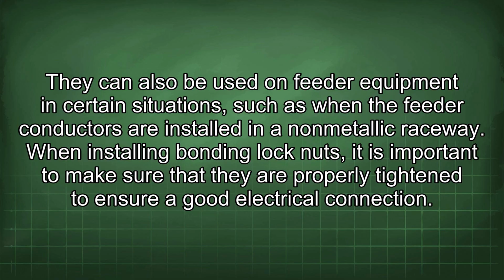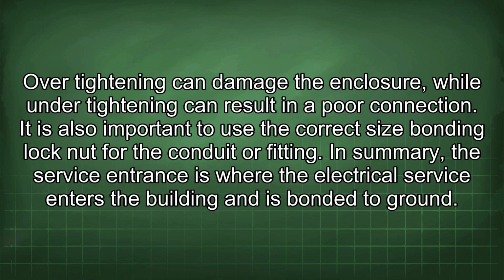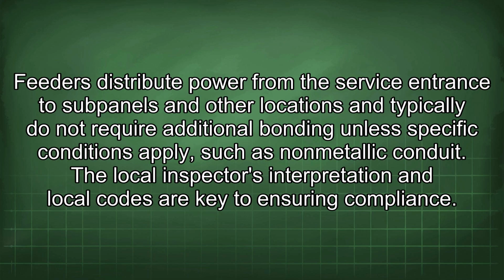When installing bonding lock nuts, it is important to make sure that they are properly tightened to ensure a good electrical connection. Over-tightening can damage the enclosure, while under-tightening can result in a poor connection. It is also important to use the correct size bonding lock nut for the conduit or fitting. In summary, the service entrance is where the electrical service enters the building and is bonded to ground. Feeders distribute power from the service entrance to subpanels and other locations and typically do not require additional bonding unless specific conditions apply, such as non-metallic conduit.